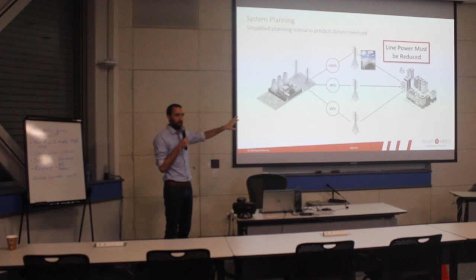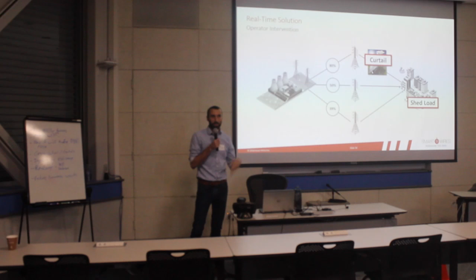Going back to Brock's earlier example, we have a simplified planning scenario predicting a future overload. We've got to reduce the power flowing on that line. As Brock said, we can curtail generation or shed load, and the long-term fixes are to build a new line, put in a legacy fixed solution like a phase shifting transformer, or do a reconductor. A reconductor, for those who don't know, is taking down the old skinny wire and replacing it with a bigger, fatter wire that has more capacity. This is probably the most common approach utilities take.